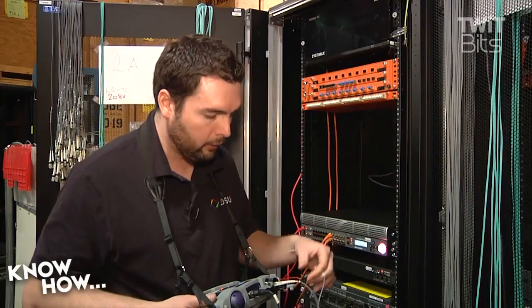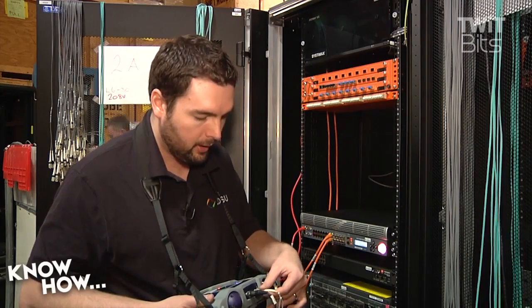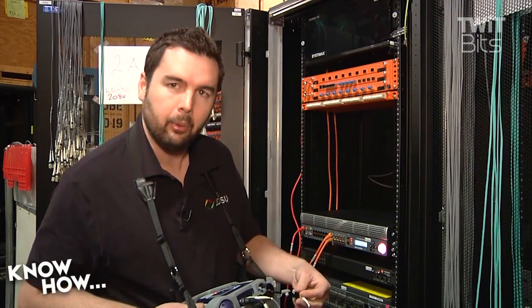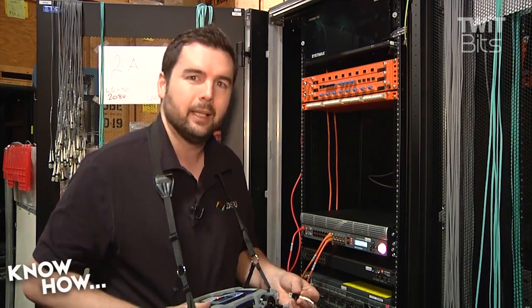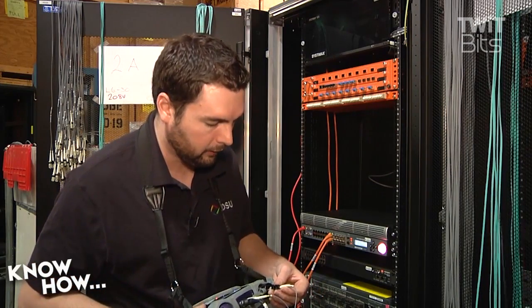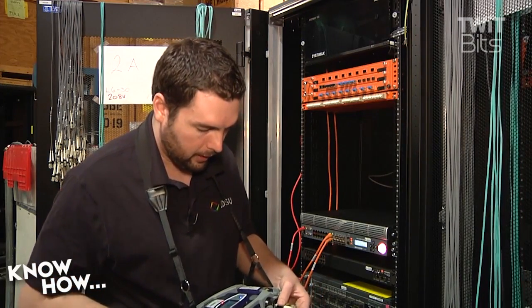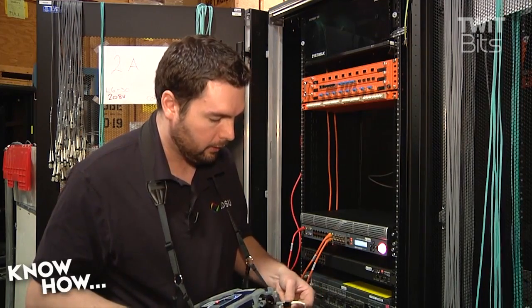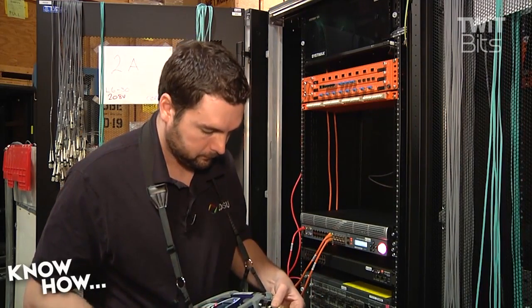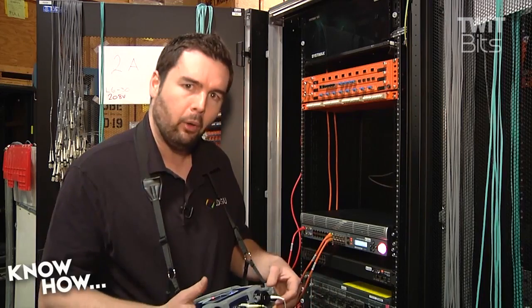Now I've validated that end is clean, so I can move it over to my power meter port—it's a nice safe place to park the connector when you're not using it. Checking the other end, this one's pretty dirty too, so I'll clean it. That's a lot better. Now both ends are ready to go.